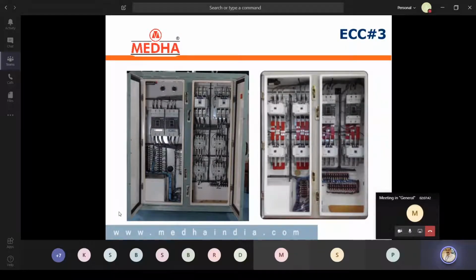As per earlier railways we have provided this, but in practice some problems were faced, because for effective engine cooling from 4000 HP to 4500 HP, the radiator fan blade size increased. Because of that current consumption also increased, so there were some tips welding in the 150 ampere contactor. So as per RDSO we went for a redesign of all the contactors with 325 ampere operation, and many cables were there. All those cables we have converted to bus bar connection. For convenience we have shifted the 2 breakers from this side to this side, and all the 6 contactors through bus bar connections.